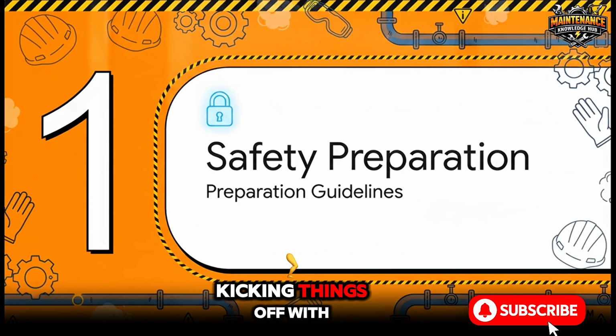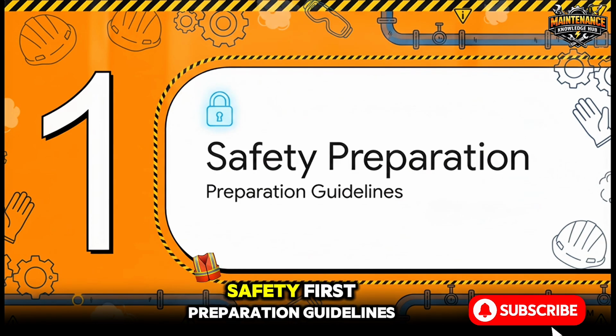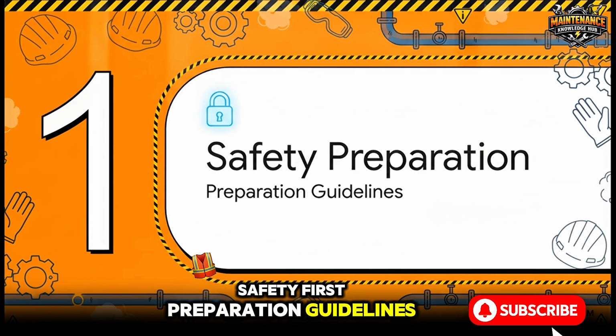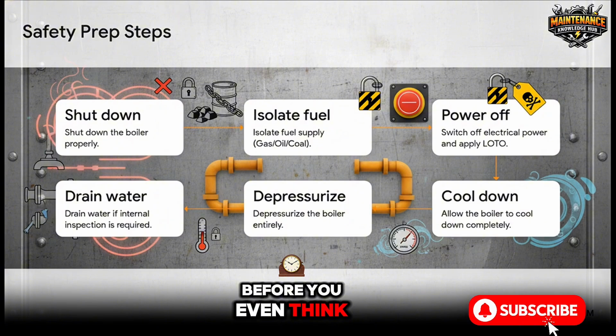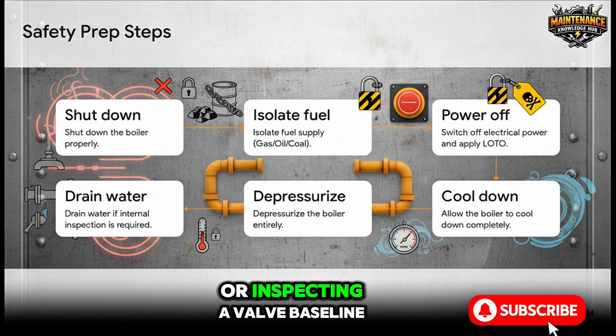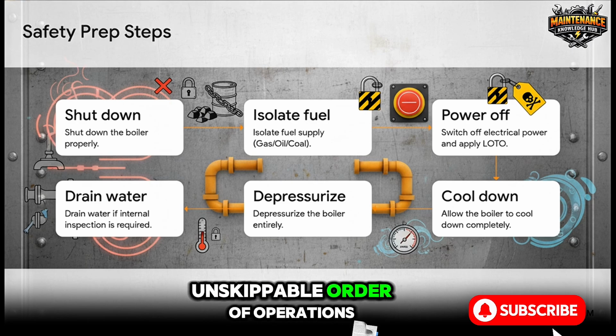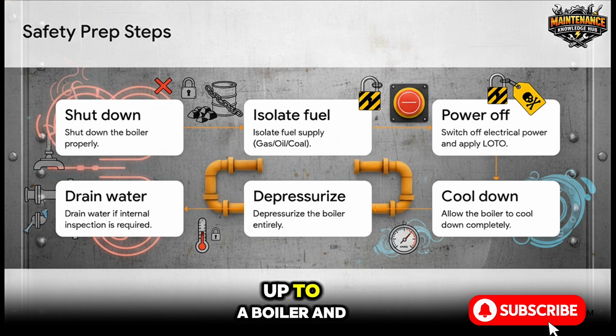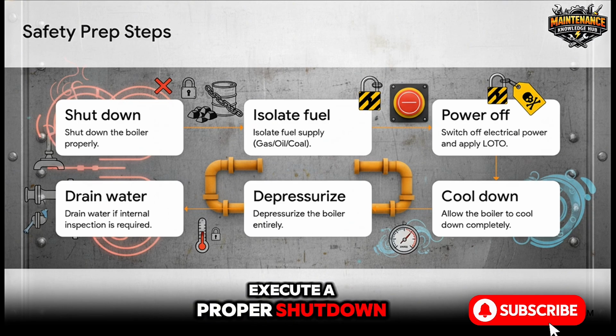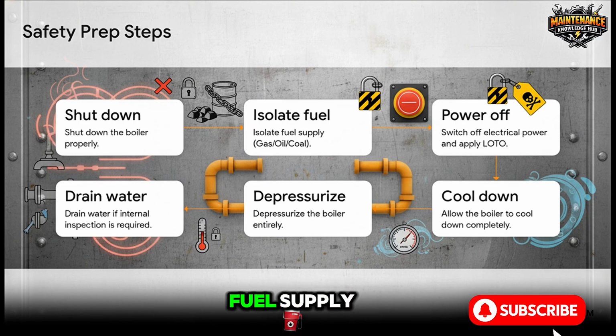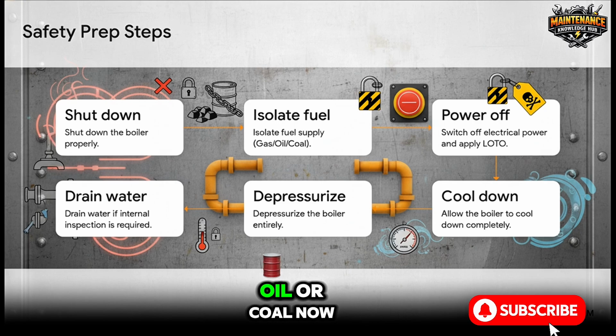All right, kicking things off with Section 1, Safety First, Preparation Guidelines. Before you even think about turning a single wrench or inspecting a valve, baseline safety is your absolute unskippable order of operations. You just don't walk up to a boiler and start tinkering, right? First up, you execute a proper shutdown. Then, you completely isolate that fuel supply. Doesn't matter if it's gas, oil, or coal.